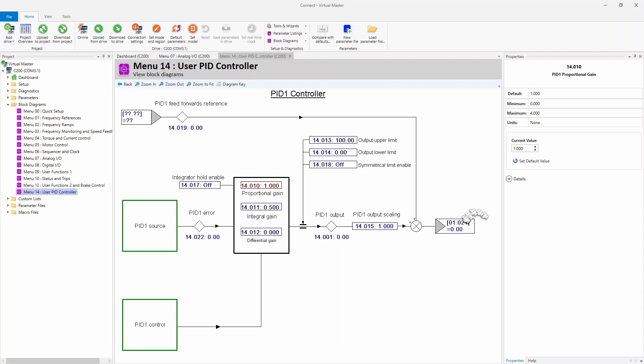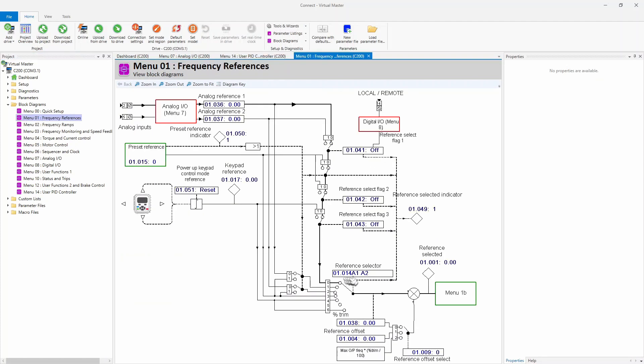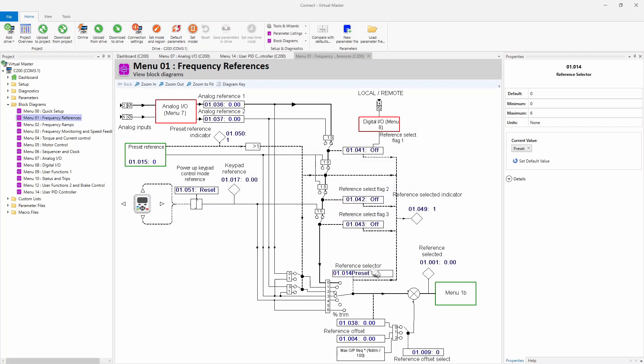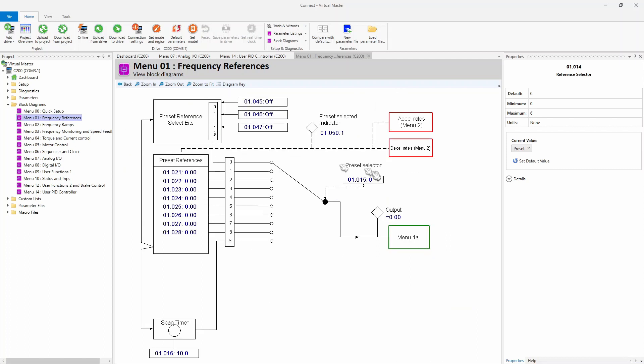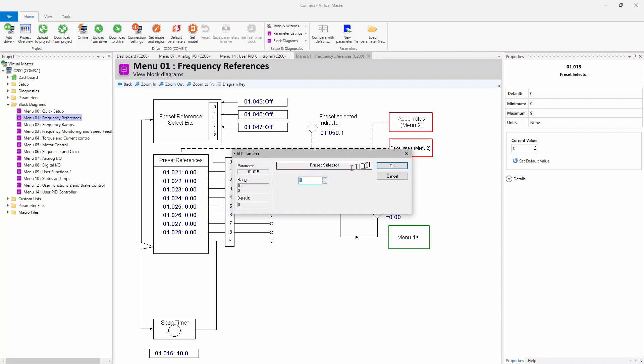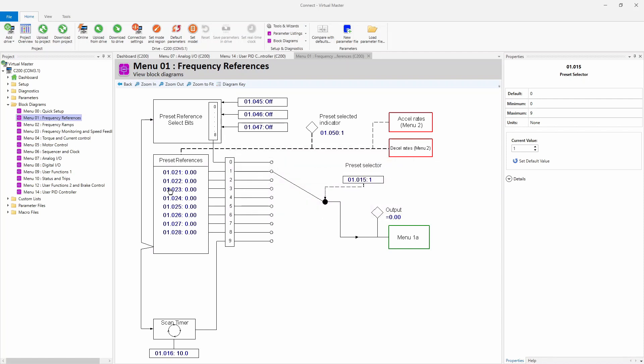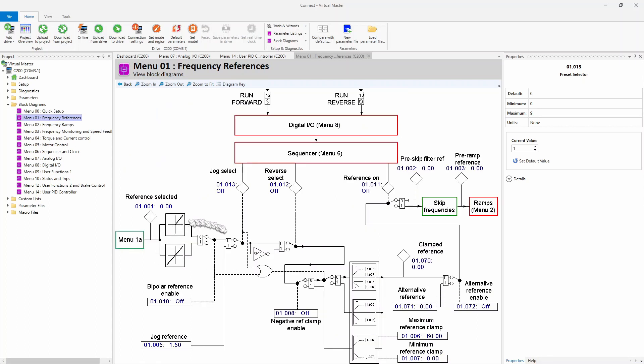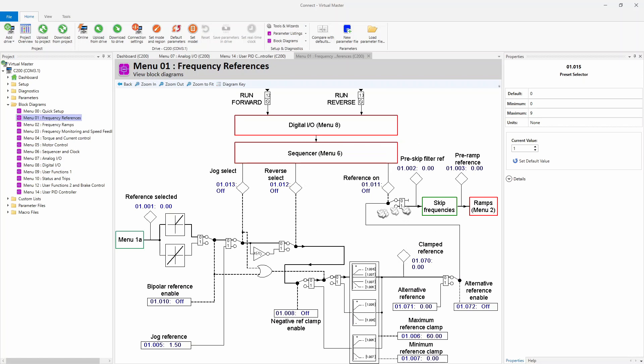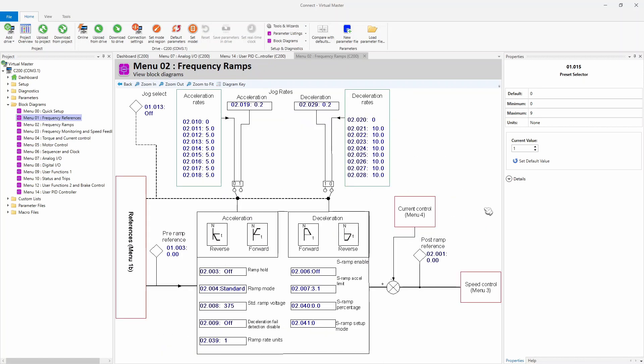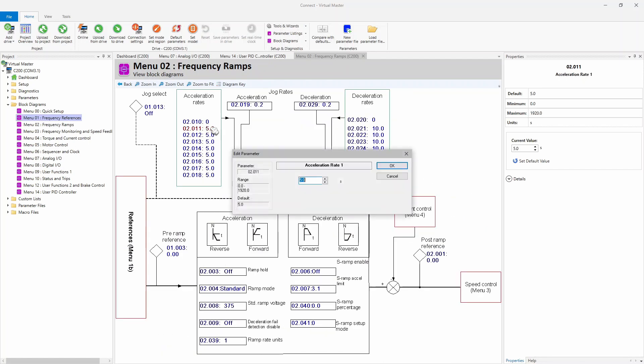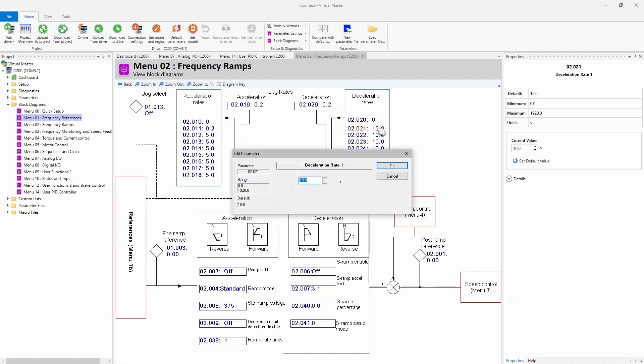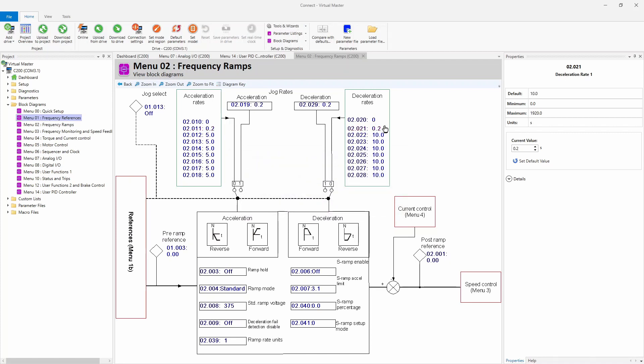There was a couple steps we haven't done yet. If we go back to menu one, we come down here, we need to select presets. Because the preset is where we're trying to get our speed reference from. If we follow it back here, we need to set this to preset one. And that is everything. So the PID outputs here, it comes through this line, it follows on through down this way, comes on out, it goes through this logic here. Basically, what this is doing is if it's given a run command in menu six, then it lets it go through. If it doesn't have a run command through menu six, it basically prevents the reference from going through. And then here's our ramps. We want a really fast ramp. It might be just better to disable the ramps completely. But I'm going to add just a little bit of ramp just because. And that is it. We are completely set up.